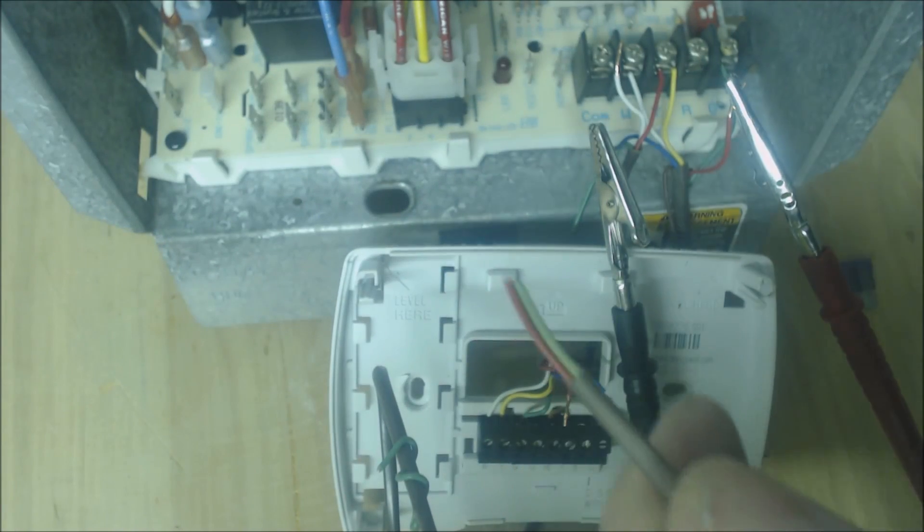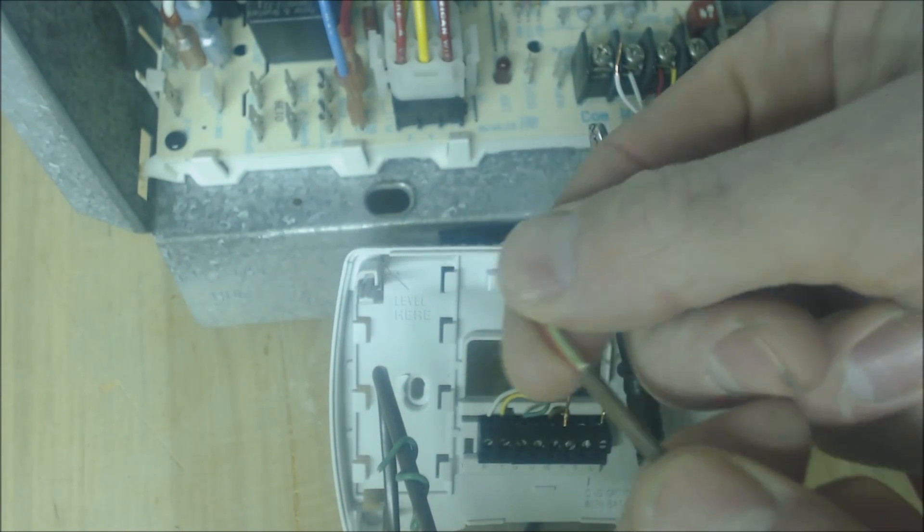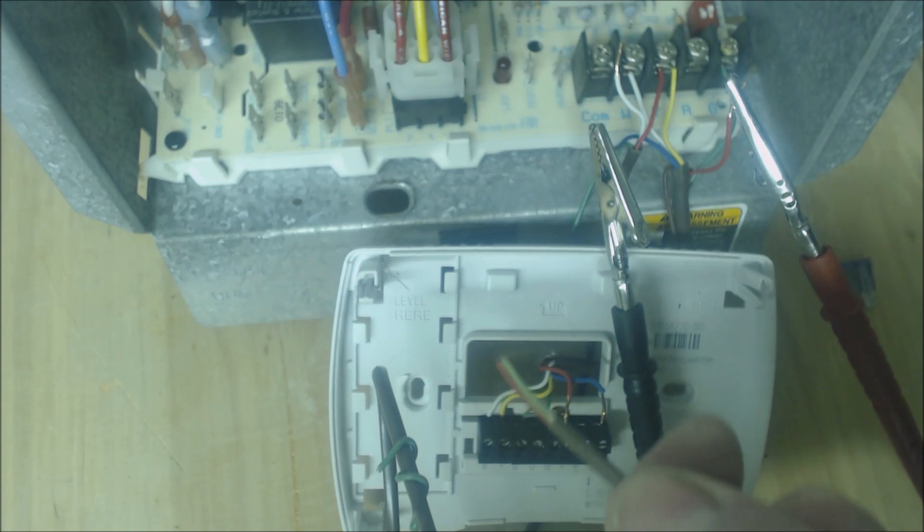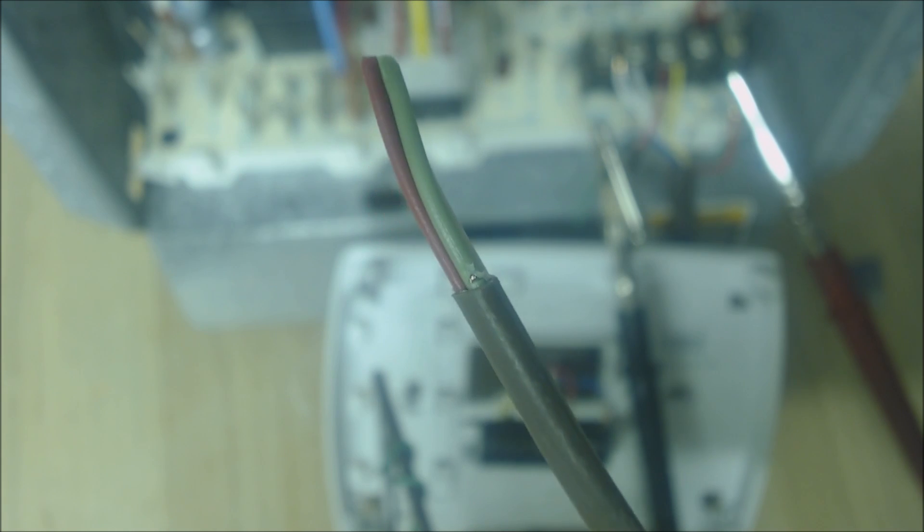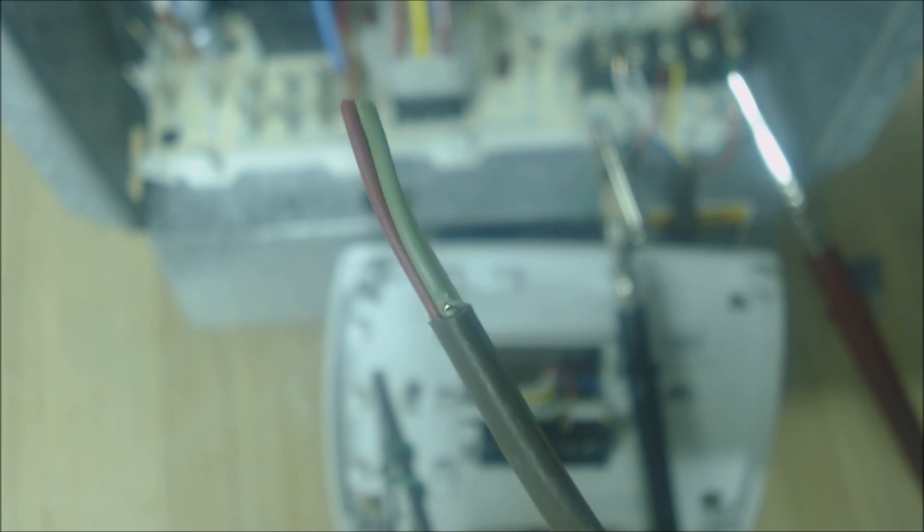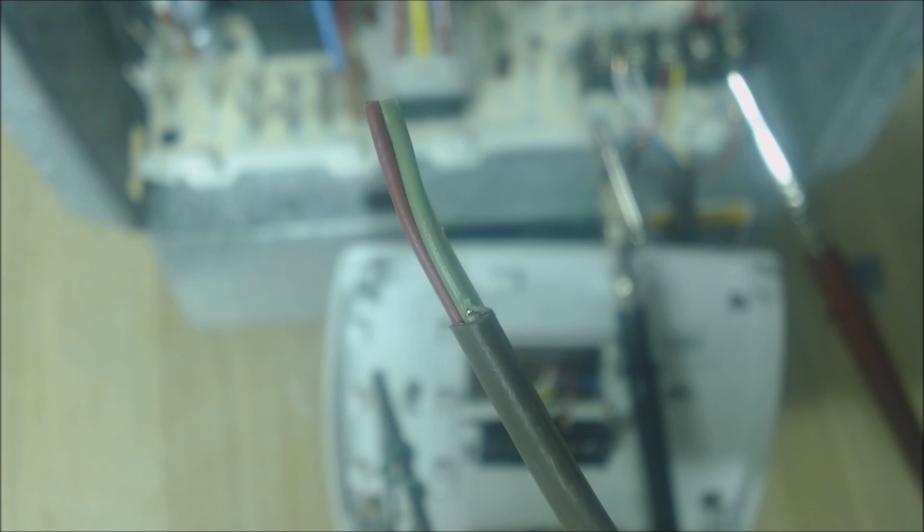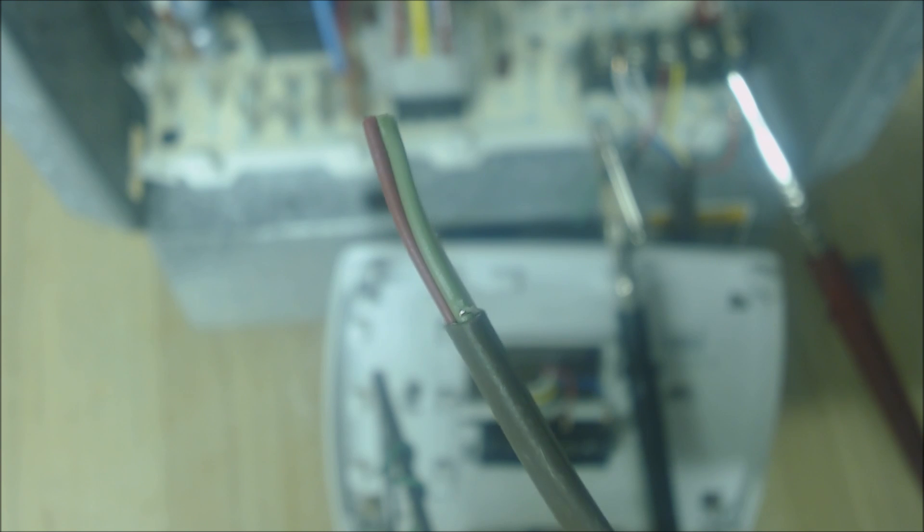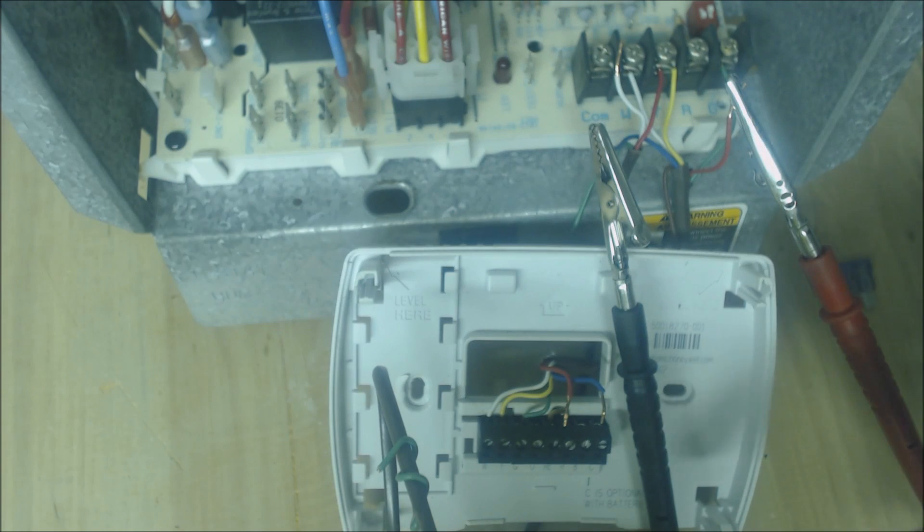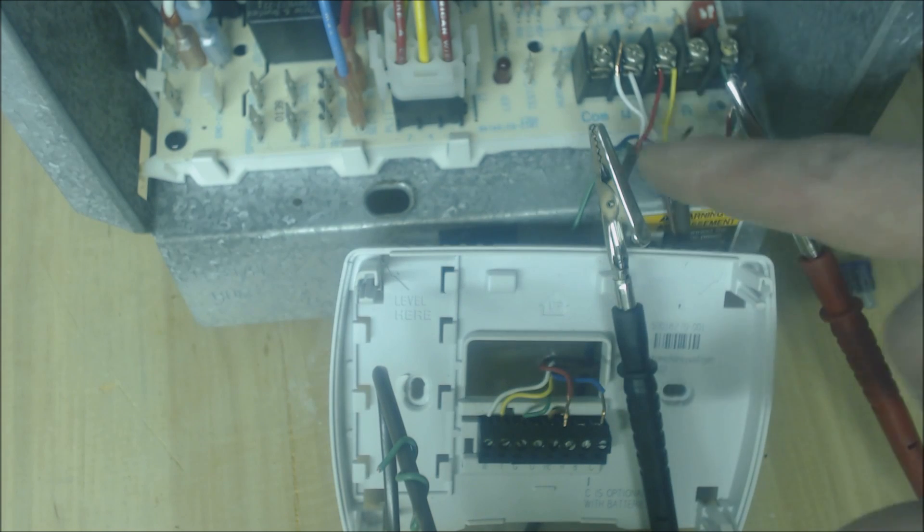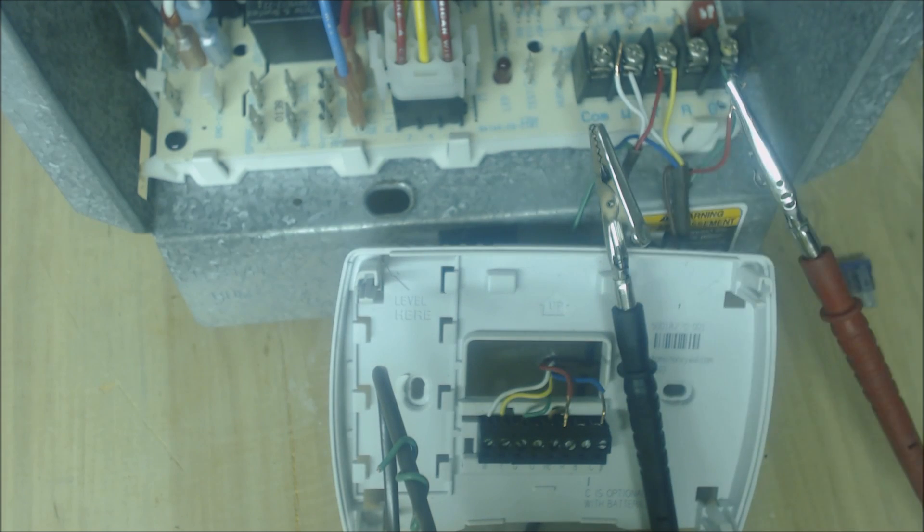If you ever come across this right here, I don't know if you can make that out, but there's a little bit of sheen to it. You can see that the wire has been nicked by us cutting the outer casing in that manner. That right there would be a problem, so you want to visibly check to make sure that the thermostat wire doesn't look like that.